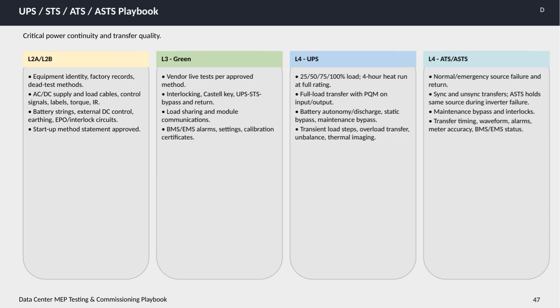Moving on to level 3, marked in green, this stage involves live vendor testing based on the approved methods. Critical elements include verifying interlocking mechanisms, Castell key functionality, UPS to STS transitions, including bypass and return sequences, load sharing, and module communications. We also evaluate BMS and EMS alarms, confirm settings, and review calibration certificates to ensure accuracy.